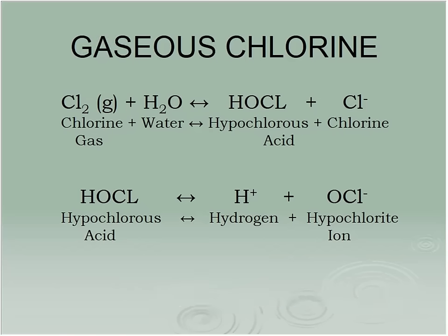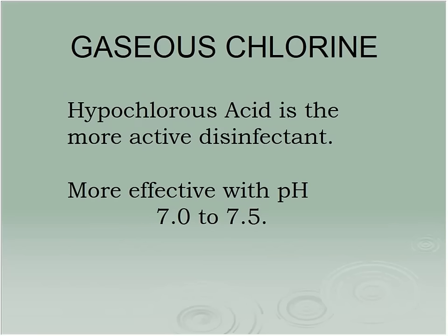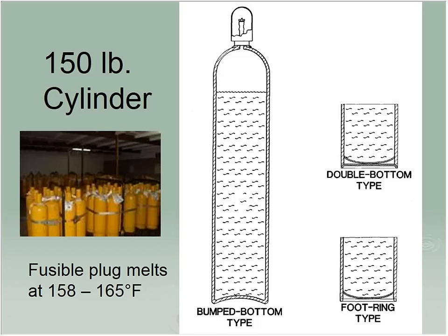But this is what happens. Take chlorine gas, mix it with water, and you form hypochlorous acid. Hypochlorous acid is the predominant disinfectant. So we want to make sure our pH is such that that is the ion we're going to generate. A pH of 7 to 7.5 is optimum. That's where we're going to generate the most hypochlorous acid out of that solution. We can go above or below that, and you tend to make more hypochlorite, which still works, but it's not quite so effective.